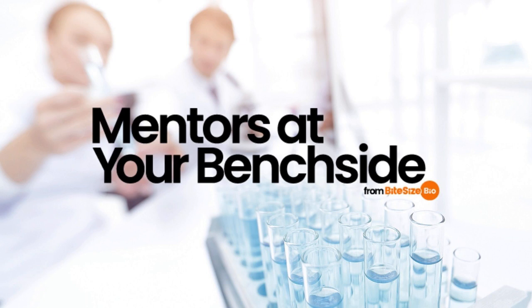So how do you calibrate? There are 2 forms of calibration, external and internal. There are 2 main options to calibrate your lab balance depending on your individual balance. Nearly all balances can be externally calibrated, but some also have the option for internal calibration. Internal calibration is performed with little to no input from the user and can be triggered manually or set automatically at predetermined times, for example overnight or during lunchtime. Check with your lab manager or lab head to find out if your scales automatically perform internal calibration, and refer to your user manual for how to manually trigger internal calibration if needed.